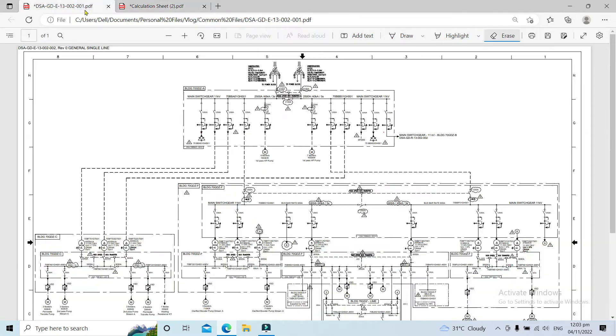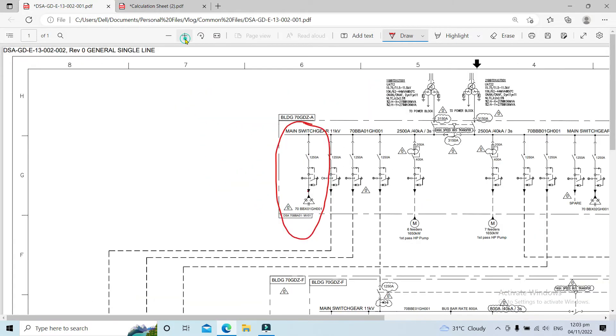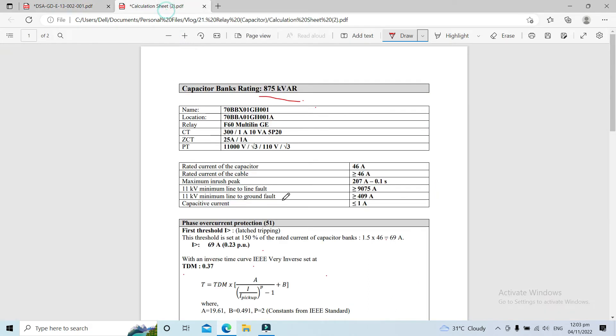Let's go first to our key single line diagram. The location of our capacitor bank is connected on the 11 kV main switchgear. These are the basic data related to our relay setting calculation for the capacitor bank feeder.